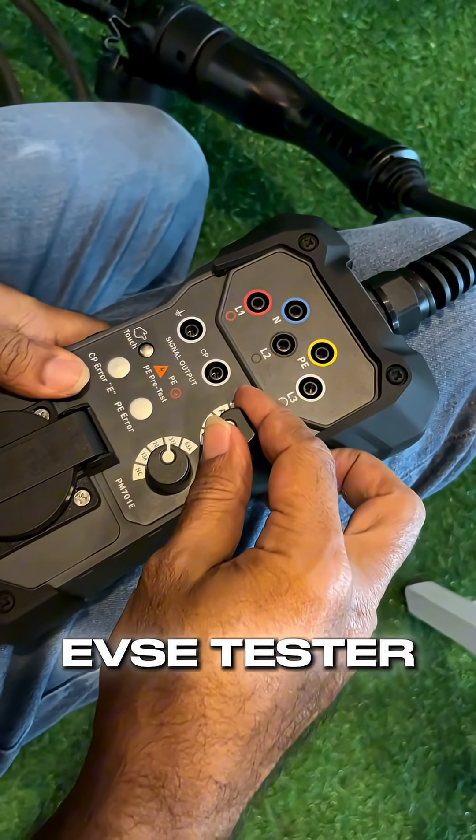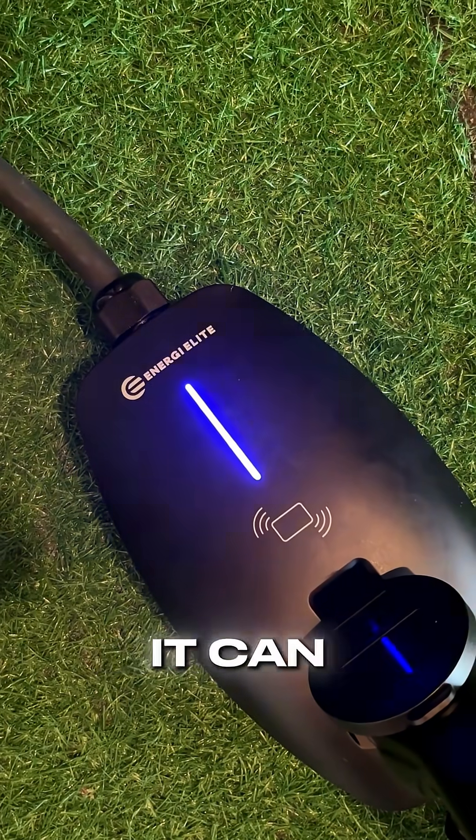Finally, we plugged it into our EVSE tester. This confirms the vital protective earth ground safety so that you don't get shocked, then simulates a car connection to make sure that it can properly start the charge.